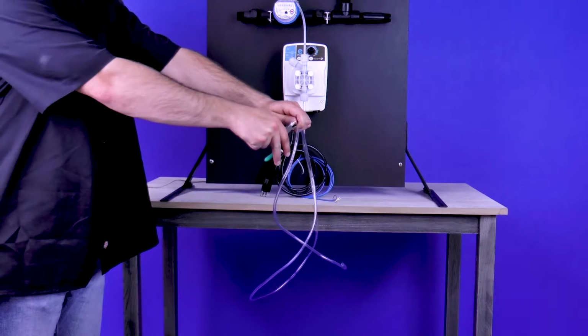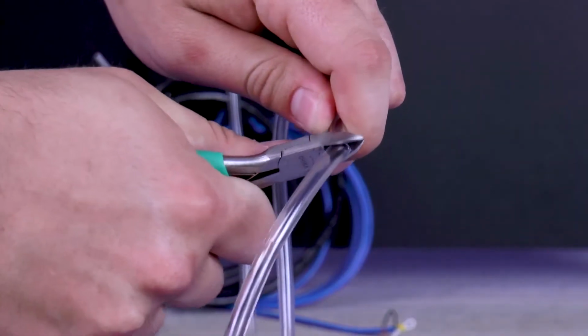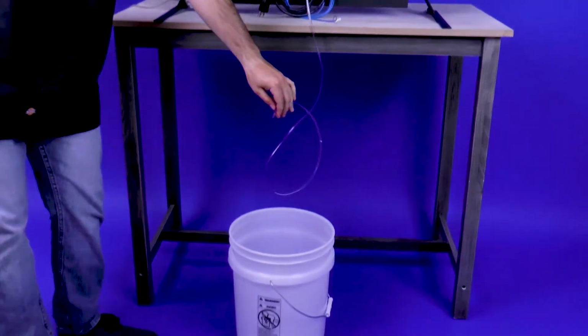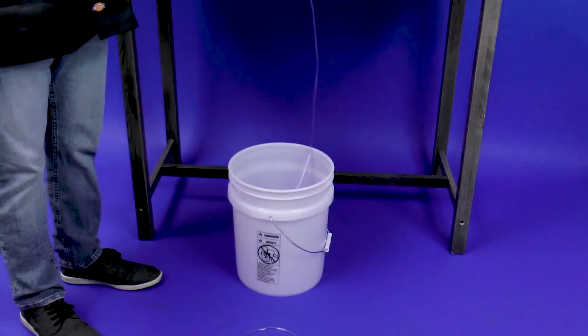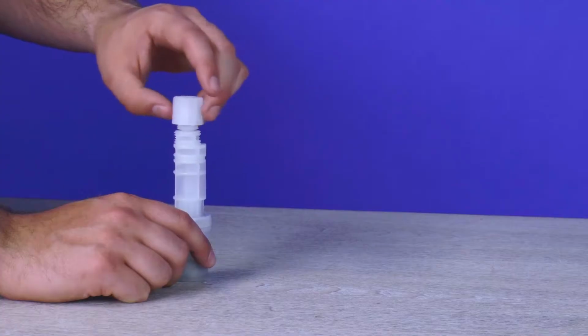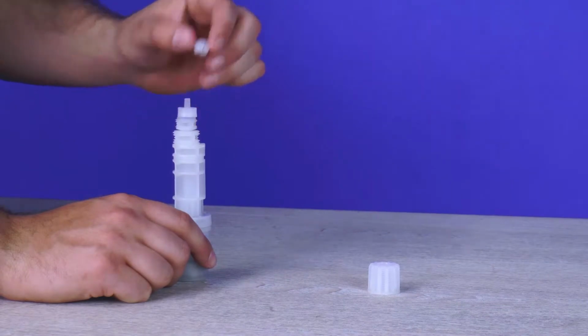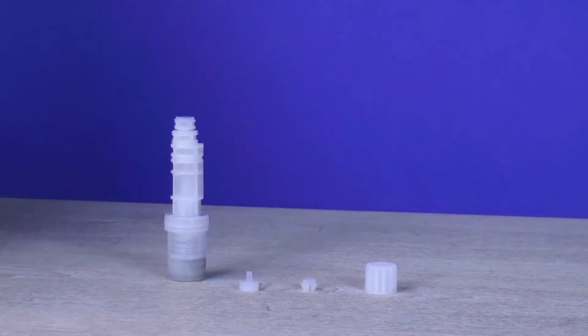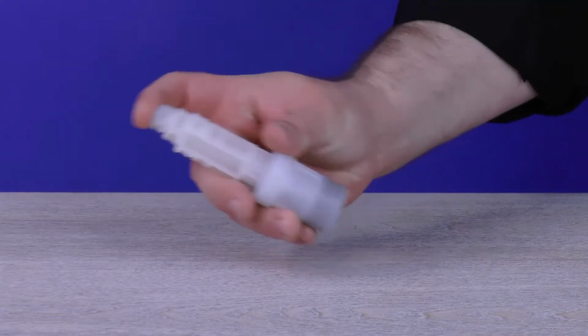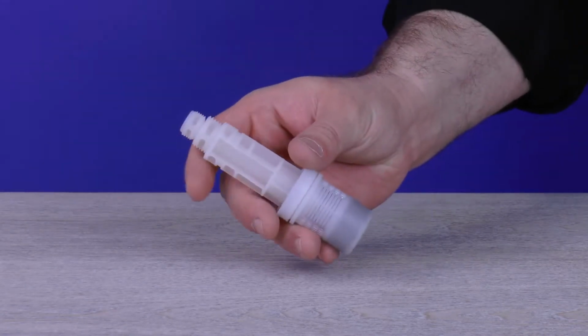Foot filter. To rebuild the foot filter, cut the PVC suction tubing connected to the suction valve so that the foot filter will comfortably sit in the chemical bucket in a vertical position. Grab the foot filter from the tubing kit and remove its tube nut, collar, and nozzle. Set the connections aside. Grab the foot filter and shake it back and forth. You should hear a ceramic ball moving freely inside.